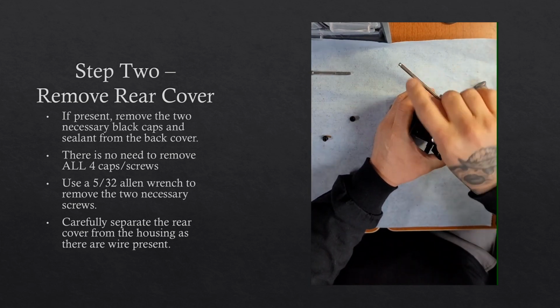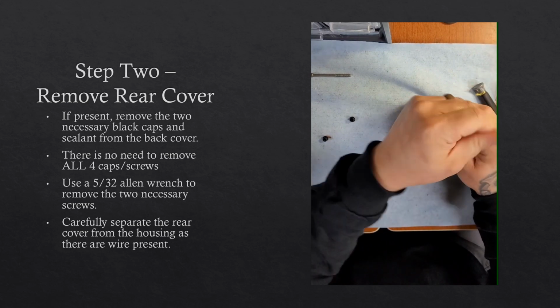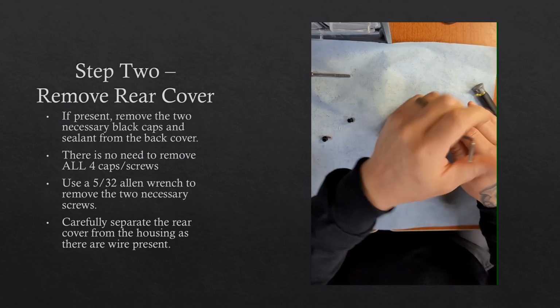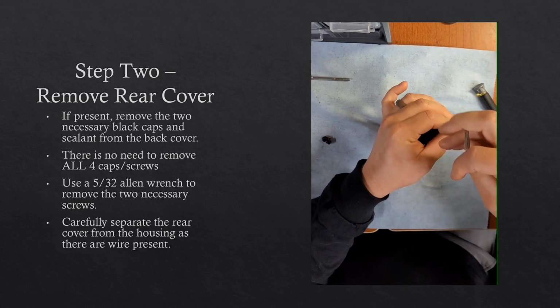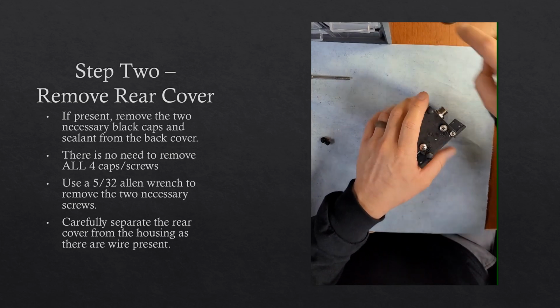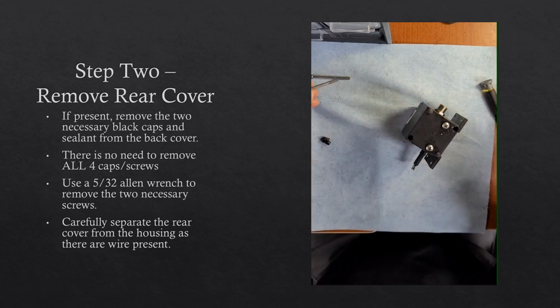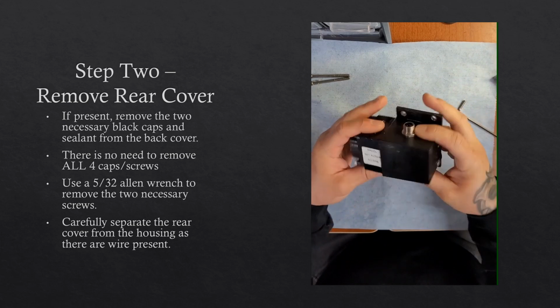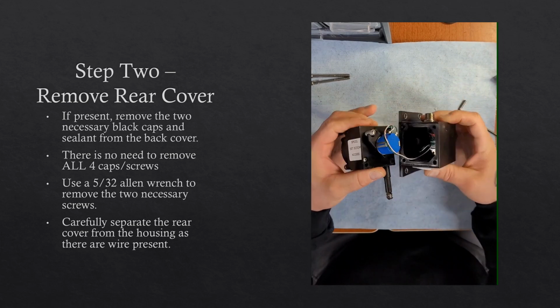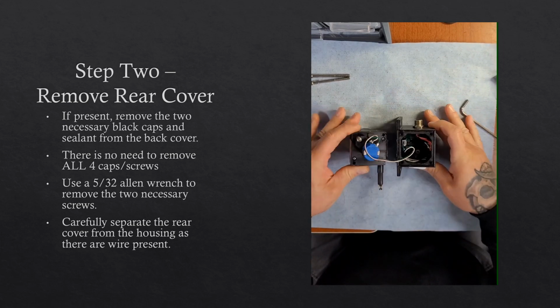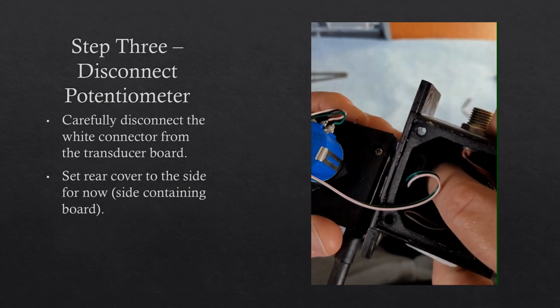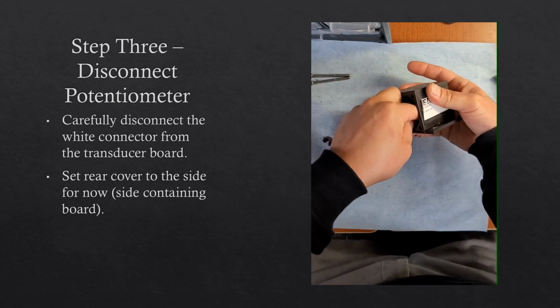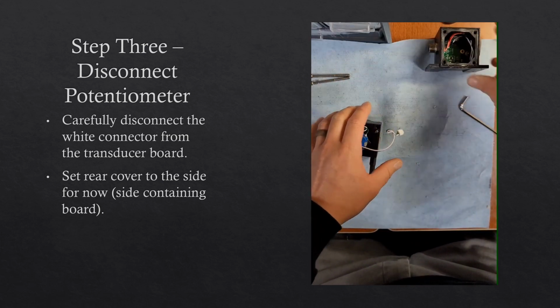Once we get those two screws out, we'll be able to separate the transducer board housing from the rest of the actual transducer. But when you do, be careful. There is some wiring on the inside for the potentiometer. Don't want to yank it apart and break those wires. As you can see, next thing we're going to do is disconnect the potentiometer from the transducer board. Pretty simple, just be careful, be gentle with it.